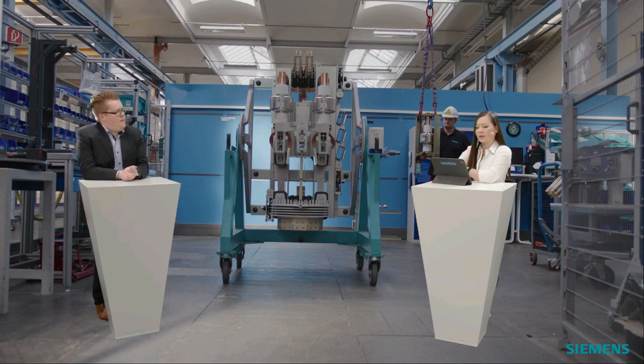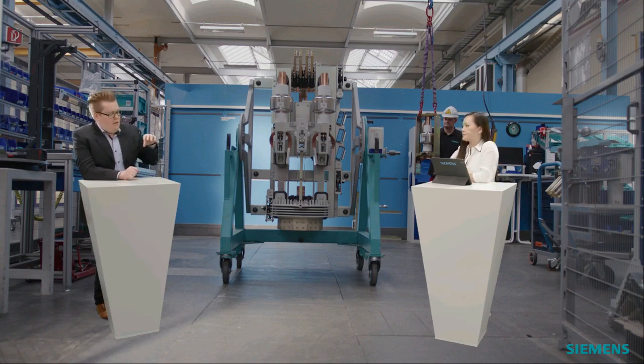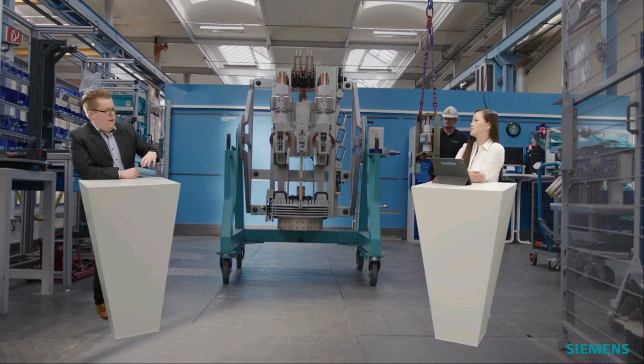All right. Another question regarding the calculation: how do you consider arc voltage in your simulation? The arc voltage is very important. The IEC IEEE standard requires us to consider the arc voltage characteristic of each circuit breaker in our short circuit calculation. So when we have our contact opening, as I said, there is this arc voltage build up, and we have to take this arc voltage into account in our calculation. Of course, this is different for SF6, and that's why it is really important.